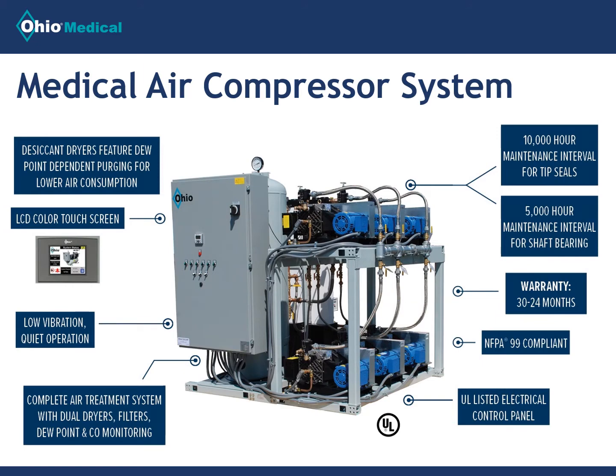Our flagship unit is the medical air compressor system. This unit operates quietly and with low vibration. The desiccant dryers have dew point dependent purging for lower air consumption. They are part of a complete air treatment system, which includes filters, dew point sensing, and CO monitoring. The scroll compressors have a 10,000-hour maintenance interval for tip seals and a 5,000-hour maintenance interval for shaft bearing. These systems are NFPA compliant and have UL-listed control panels. Our warranty is 30/24.